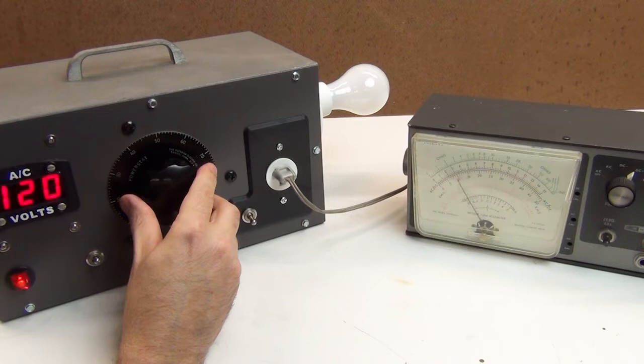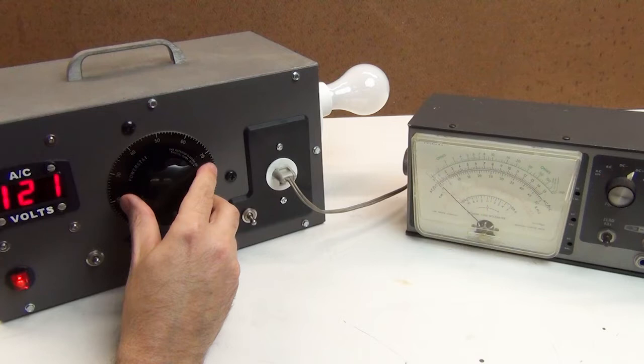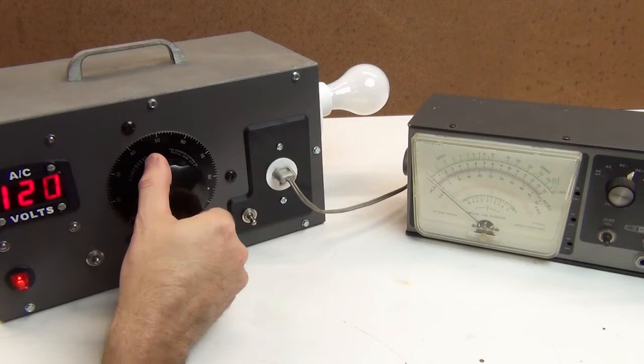However if the bulb starts glowing brightly then that likely means the DUT has an issue possibly even a direct short and you need to stop the test and investigate.